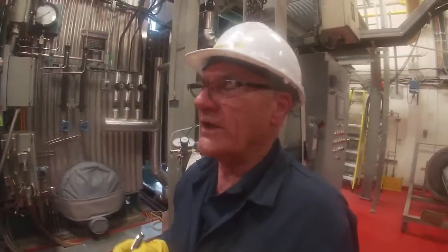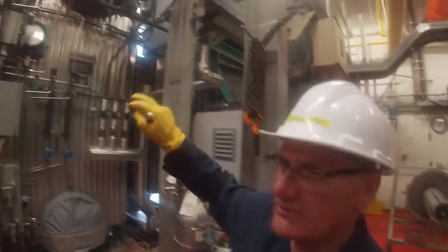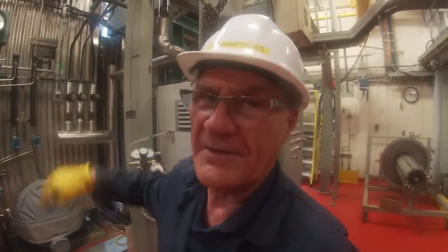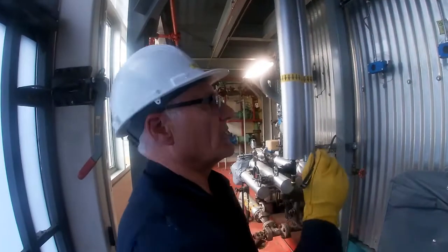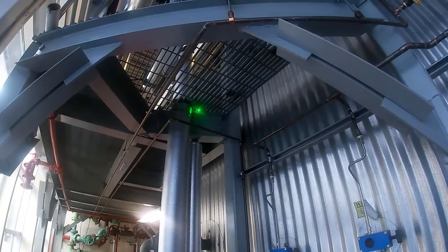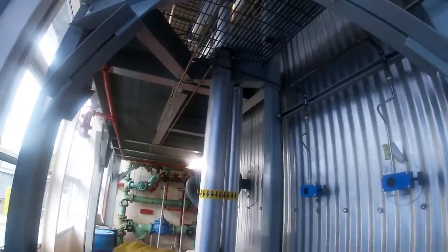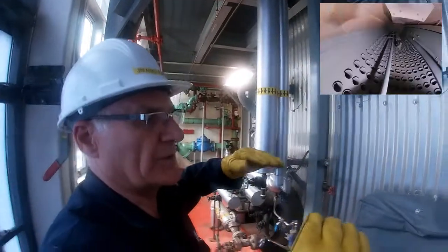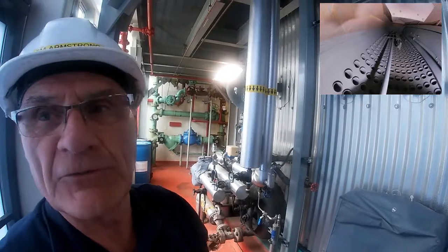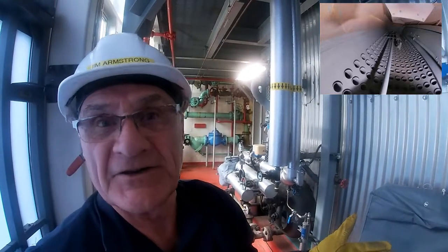One more thing. We are now going to go and look at the blowdown, the constant blowdown, which is coming out the back of the boiler. So that's the next step. So we'll go around the back. Okay? So the CBD, continuous blowdown, is coming from here. It comes from the upper floor. It comes from the bottom of the drum. The actual tap goes across the drum, and it's just below where you normally run the water. It's usually just under the 0 mark, and we run ours at +3. It's probably down at -5 centimeters, something like that.